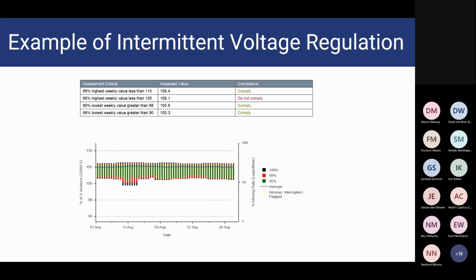So here's an example of intermittent voltage regulation. This is an example of a measurement point where the 95th percentile upper value, or maximum value, is exceeding the 105% limit. Again, as we said, the 95th percentile 10-minute RMS voltages need to be between 95 and 105% of your declared. In this case, we can clearly see, looking at these green bars that define the minimum and maximum 95th percentile value, that the value is above the 105% limit, and therefore not complying. So for this period, the maximum value was measured as 106.1.